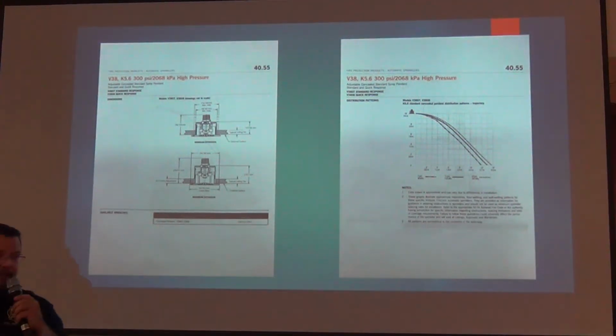If anybody has a chance to go to Viking in Hastings, they will show you this, and it is awesome to see because it actually works. They set up 1 square foot containment, basically trash cans, throughout the coverage area, and with the head active, it has to have the same amount of water in each of those. So that's where coverage and obstructions are very important to make sure you are clear of, because we need consistent coverage of water across the entire area.